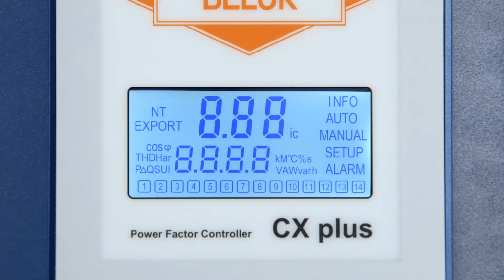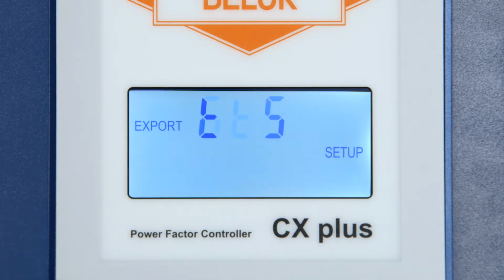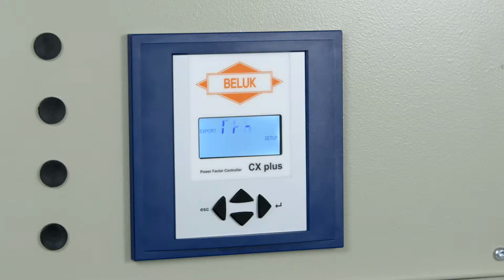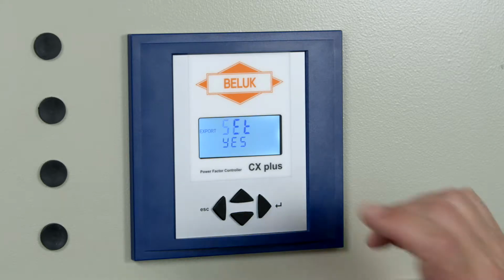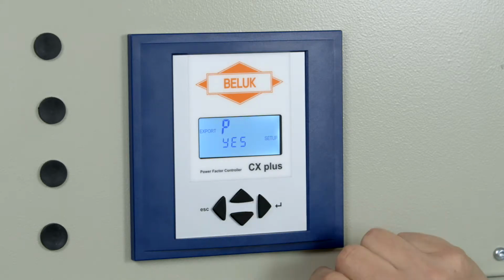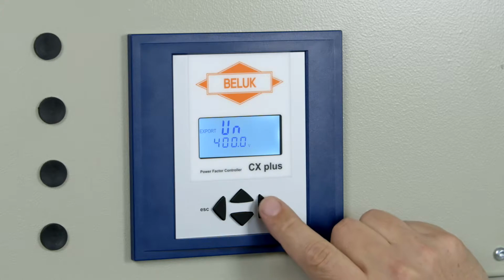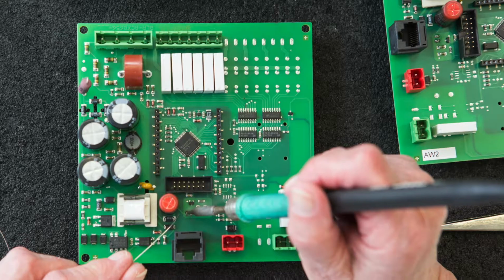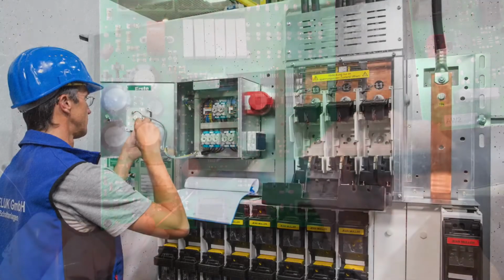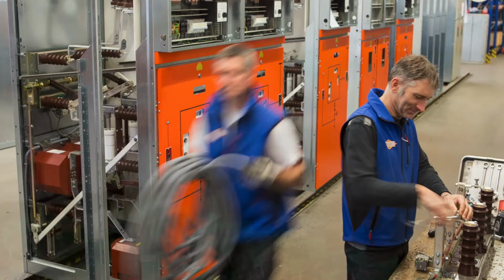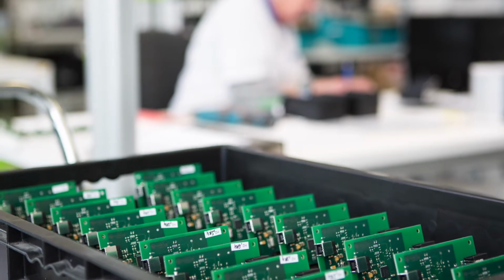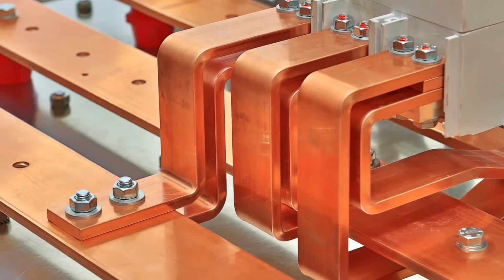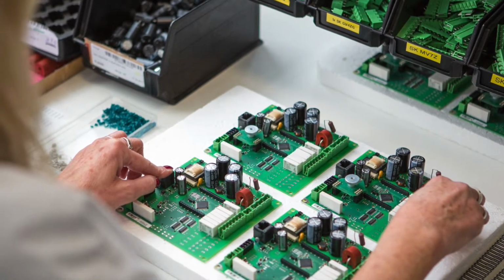Avoid mistakes. Set up a perfectly functioning compensation system quickly and safely. This is the goal of the user-guided commissioning of the Power Factor Controller BELUK CXplus. Regular devices do not interact with the user during commissioning. The user already needs to know which parameters have to be set up or where he or she has to look it up in the manual.